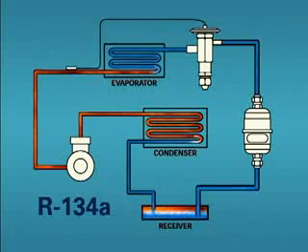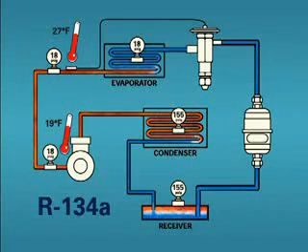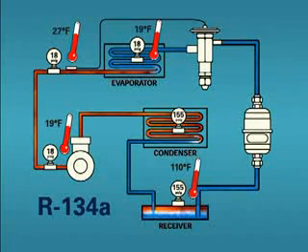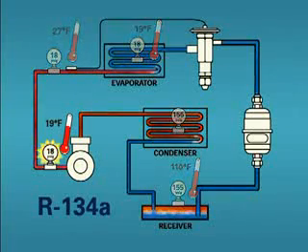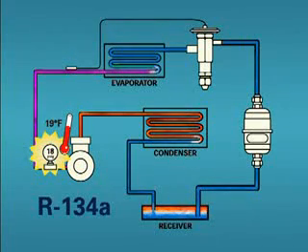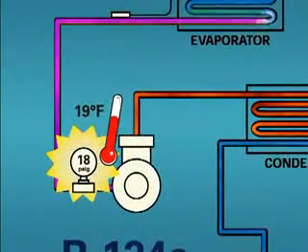Understanding the refrigerant pressure-temperature relationship in the various parts of a system will help identify and pinpoint problem areas. Because the values at the inlet of the compressor indicate a saturated condition, we know we have a problem. In this case, we have floodback, because in the suction line, the refrigerant should only exist as a vapor.